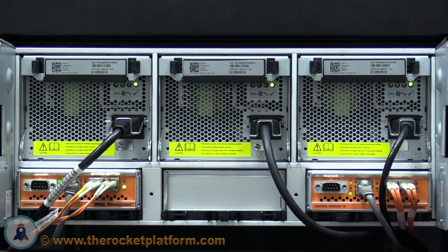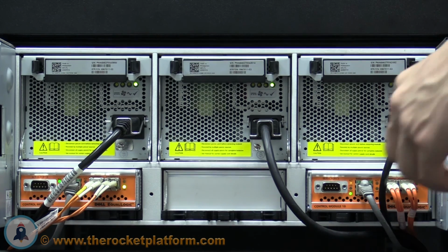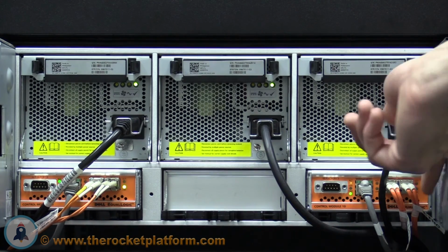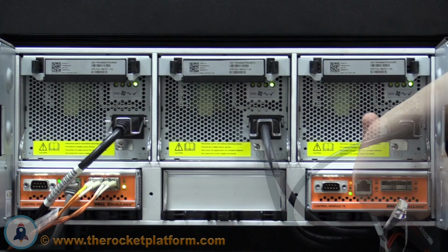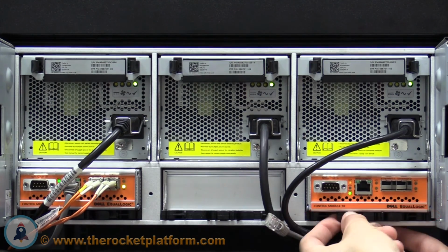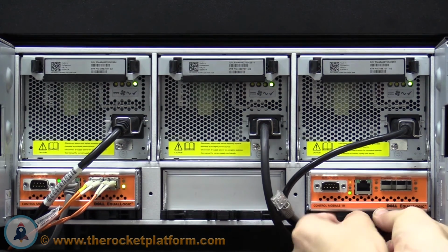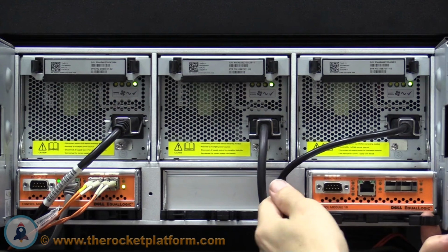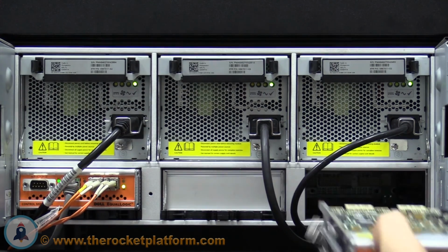Once you have confirmed which of the control modules are faulted, label the network cables according to how they are currently oriented. After you have labeled your cables, remove them from the ports. You will see two small black levers with tabs attached to them. Pinch the two tabs away from the center of the controller while pulling the levers towards you. Once the levers are extended fully, pull straight back on the controller until it has been removed from the system.